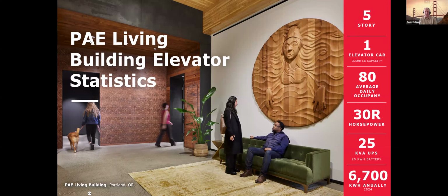So some specs on our elevator, to give a sense of how big or small it is: we just have one elevator car, a 3,500 pound capacity car. Looking up the specs, I think it's around 12,000 pounds total weight. Post-COVID, the building is returning to office but not fully, so it has about an 80 daily average occupant count. The horsepower rating of the elevator is 30. We have a 25 kVA rated UPS with 20 kilowatt hours of battery energy storage, and our elevator system uses 6,700 kilowatt hours annually — that's just for the elevator, not the whole building.